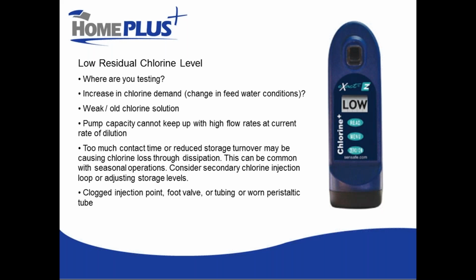So think of a campground in the winter that goes from providing thousands of gallons a day to now providing a couple hundred gallons a day for a caretaker, but may still have the same size of reservoir. That reservoir is going to allow for so much contact time because of low turnover that the chlorine is going to dissipate. You can solve that by adding secondary chlorine injection right into the reservoir, boosting it as it drops.